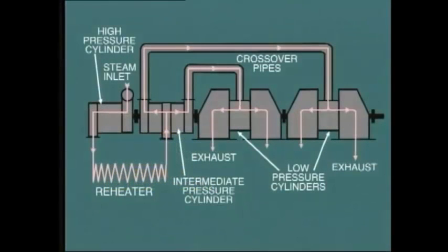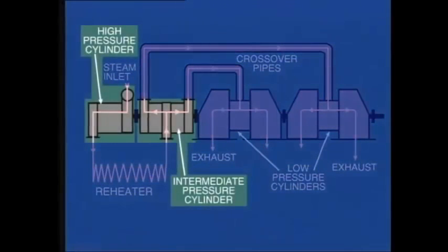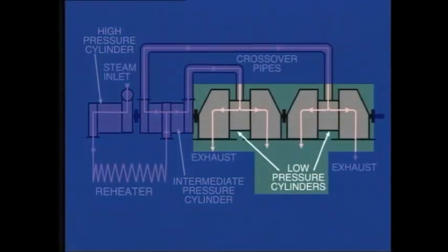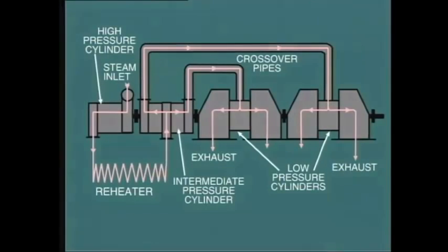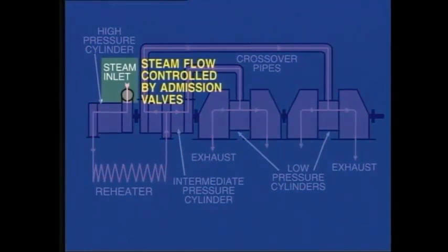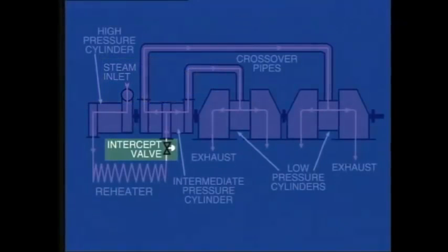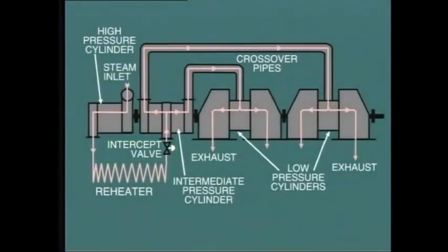As turbines become bigger and bigger, it is necessary to add yet further cylinders, and the arrangement shown here is typical for machines in the 500 to 600 megawatt range. As you can see, we have separate high pressure and intermediate pressure cylinders, and also it has become necessary to add a further low pressure cylinder in order to handle the high volume of steam. With all of the configurations shown, the general control of steam flow through the turbine is achieved by adjusting the admission valves at the high pressure inlet. However, note that with reheat units, additional control valves, known as intercept valves, are fitted at the inlet to the intermediate pressure cylinder for protection purposes. We'll be discussing this in detail when we look at control and protection in the next module in this series.